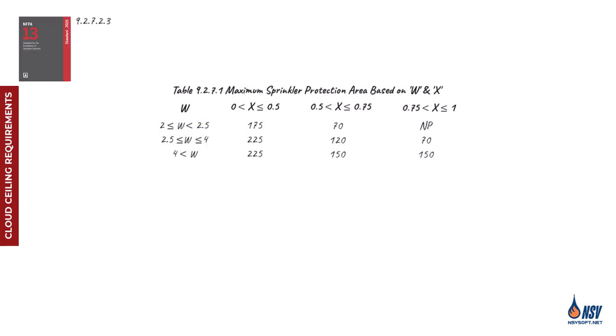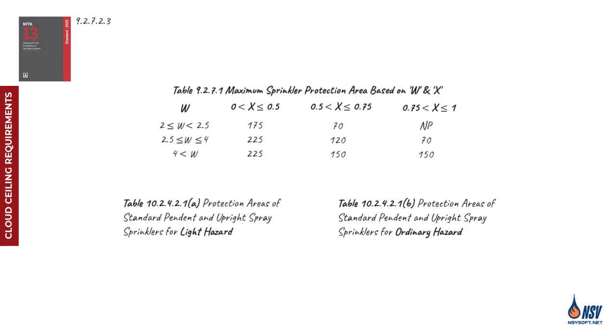It's important to note that the coverage area determined from Table 9271 must be compared against the maximum coverage limits allowed for light and ordinary hazard classifications, as outlined in Chapter 10 of NFPA 13. The smaller of the two values should be used as the final threshold for the coverage area of sprinklers installed beneath the cloud ceiling.